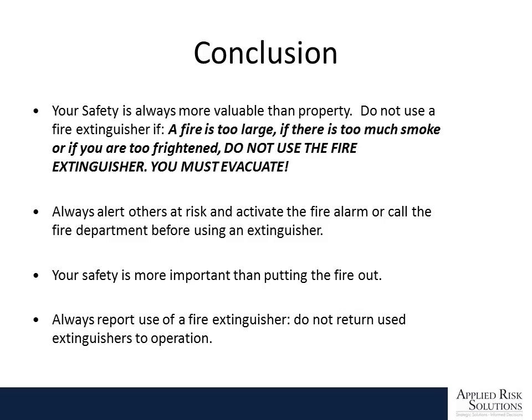Conclusion: your safety is always more valuable than property. Do not use a fire extinguisher if a fire is too large, if there is too much smoke, or if you're too frightened. Do not use the fire extinguisher in these situations. Evacuate. Always alert others of a risk and activate the fire alarm or call the fire department before using the fire extinguisher. Your safety is more important than putting out the fire. Always report the use of fire extinguishers. Do not return used fire extinguishers to the operating storage location.